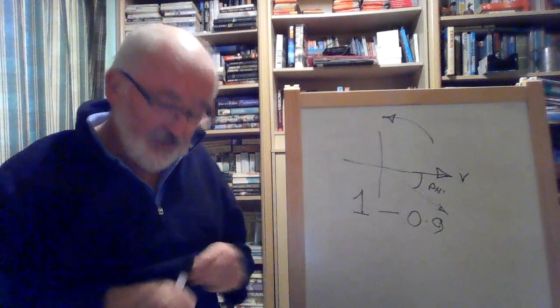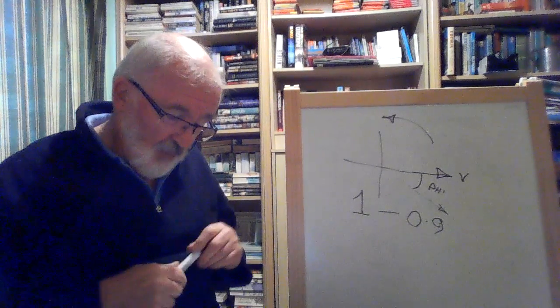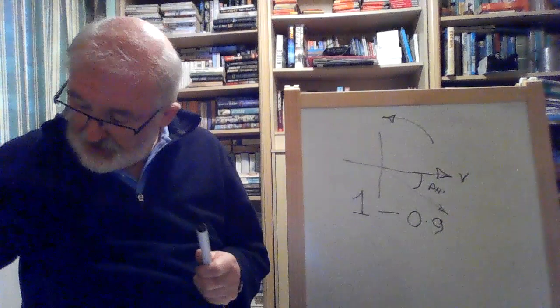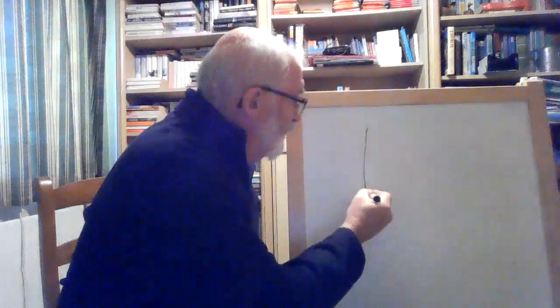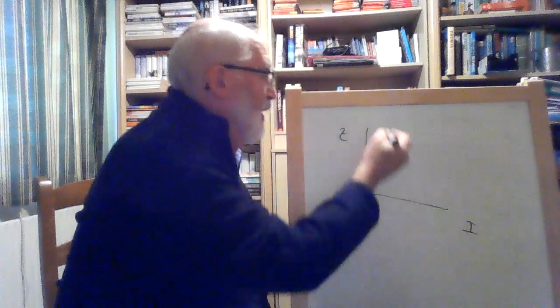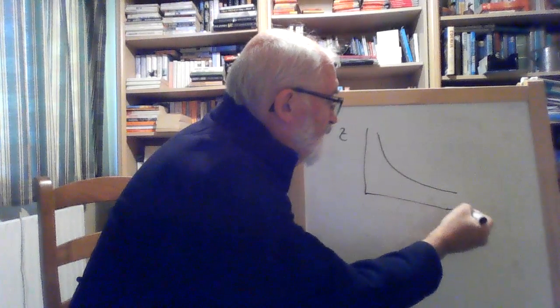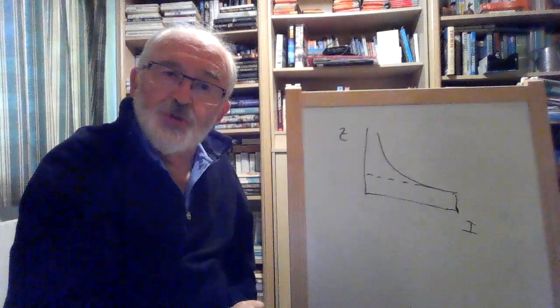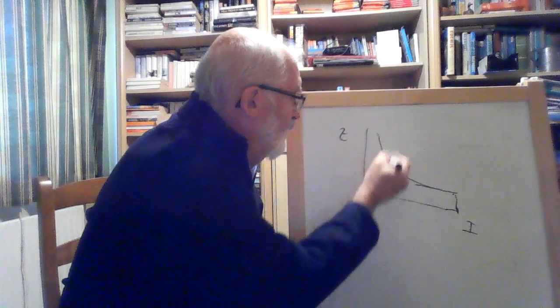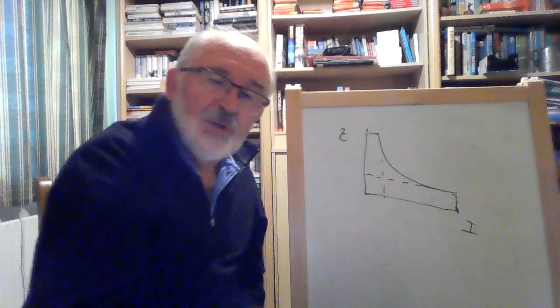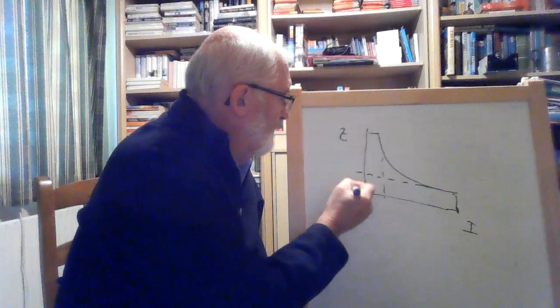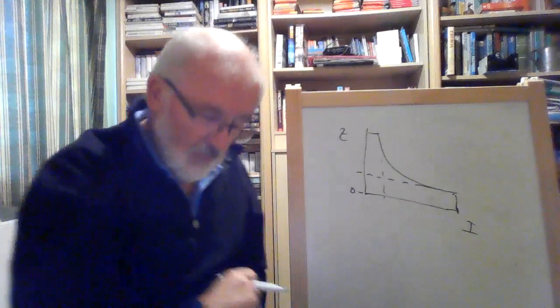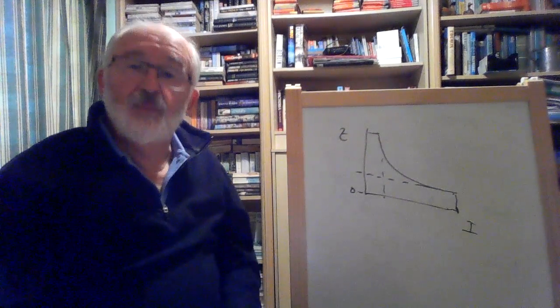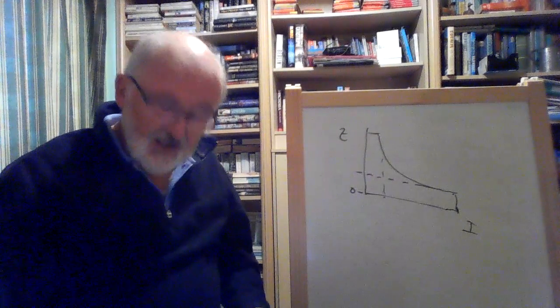Generator protection itself comes in a number of forms. We have an overcurrent inverse time, which means that the bigger the current, if we measure time up there and the current along there, what we get is a curve like that. So if the current is very, very high, it will cut out in a short time. And if the current is lower, then we will put a time delay in and it will shut down in a longer time. Okay, that's the first one. Overcurrent inverse time. That forms part of what we call the protective discrimination system that's on board.